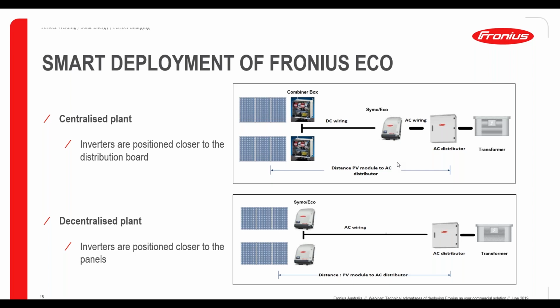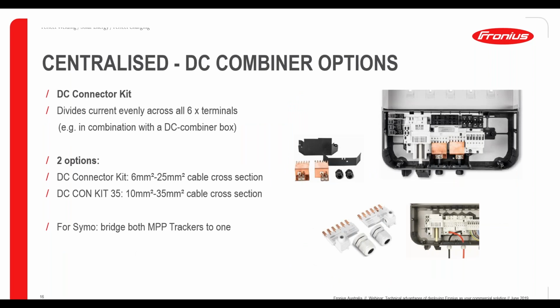In terms of the centralized scenario that we had before, meaning that the combining and fusing happens before the inverter, you can actually have DC connector kits. What this will enable you to do is utilize all of the different connections or inputs on the DC side of the inverter. So you could go up to, for example, 25 square mil on one particular option, and then the lower one there, you can go up to 35 square mil cable cross section. That would typically be used mainly only for an Eco.